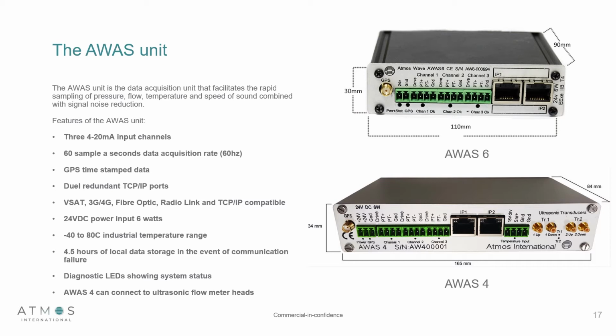It's GPS time stamped, which means we know exactly to a very specific time when each event occurred, which is again important for leak location. It's got dual redundancy for communication. We can work with an array of communication from VSAT, 3G, 4G, fiber optic, radio link, and TCP/IP compatible. It can work in extreme temperatures from -40 to +80. And also when we have a communication failure, it has built-in flash memory, and it can store 4.5 hours of local data. Once that communication is re-established, the data will be pushed back and reanalyzed. It has a simple diagnostic array of LEDs for maintenance purposes, and our AWAS 4 unit can connect directly to ultrasonic flow meter heads if required.